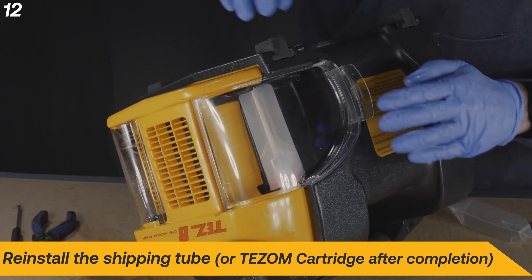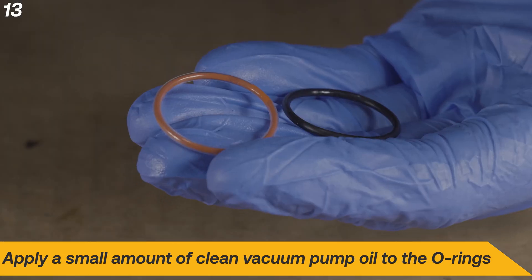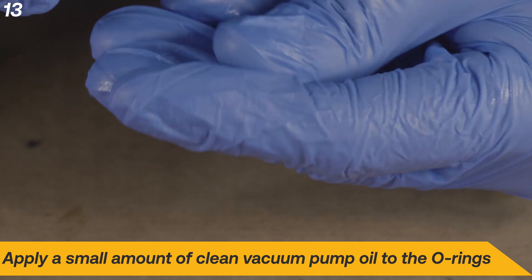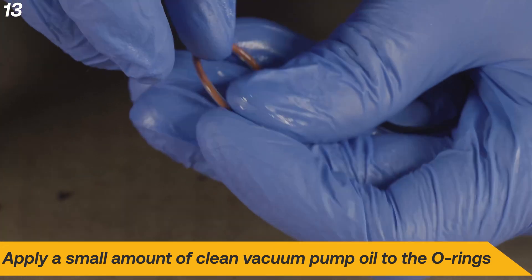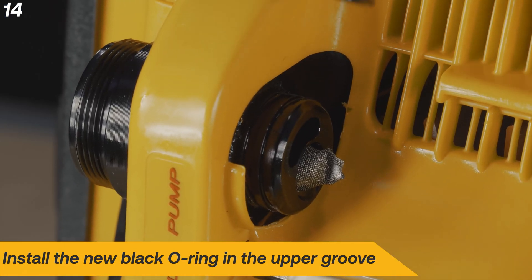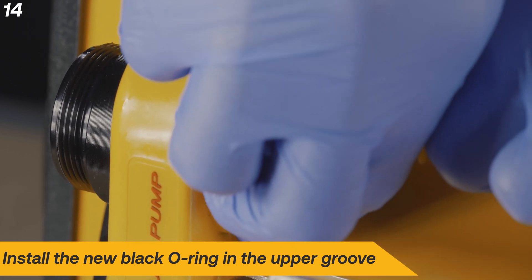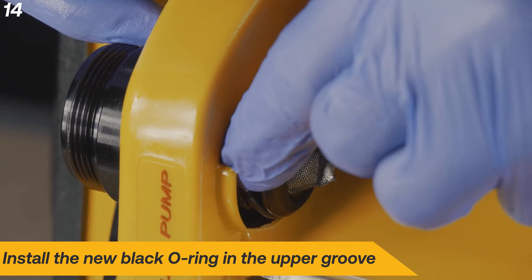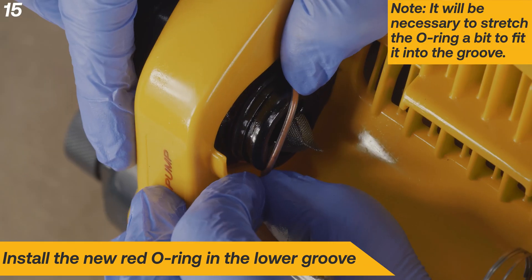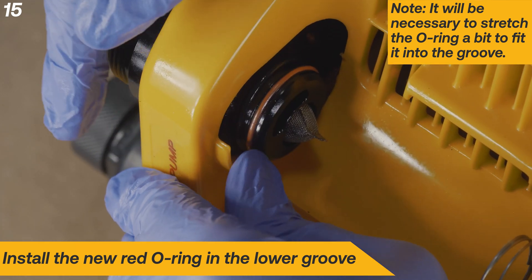Reinstall the shipping tube or TEZOM Cartridge. To install the debris tube O-rings, begin by lubricating them with a small amount of vacuum pump oil. Install the new black O-ring into the uppermost groove on the fitting. Install the red O-ring into the lower groove. It will be necessary to stretch the O-ring to get it in place.